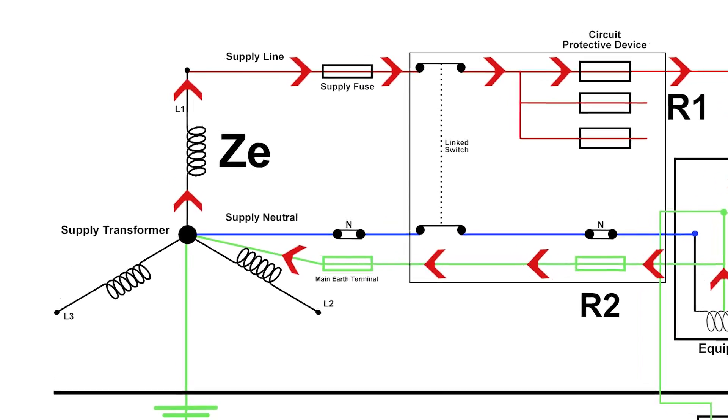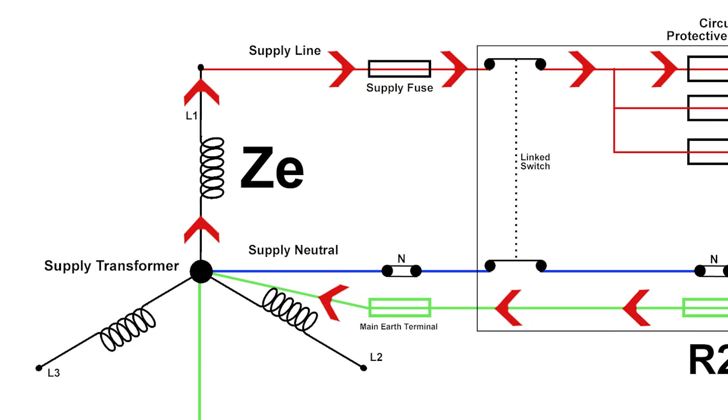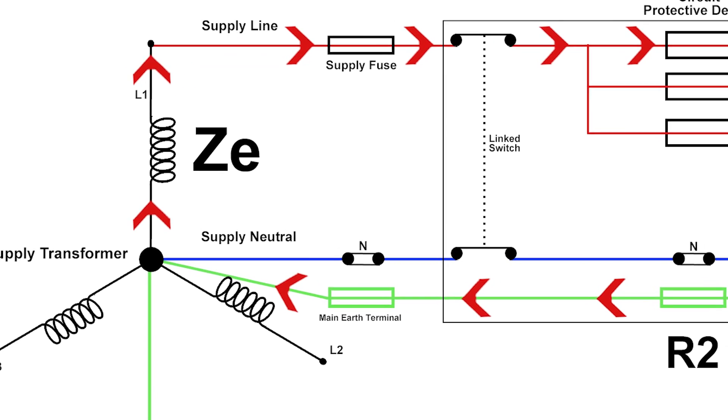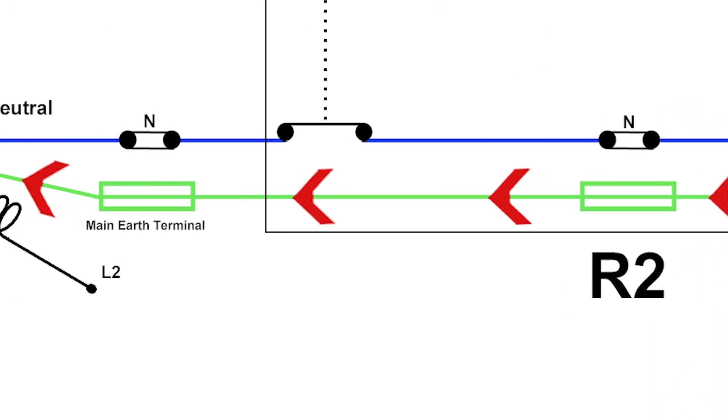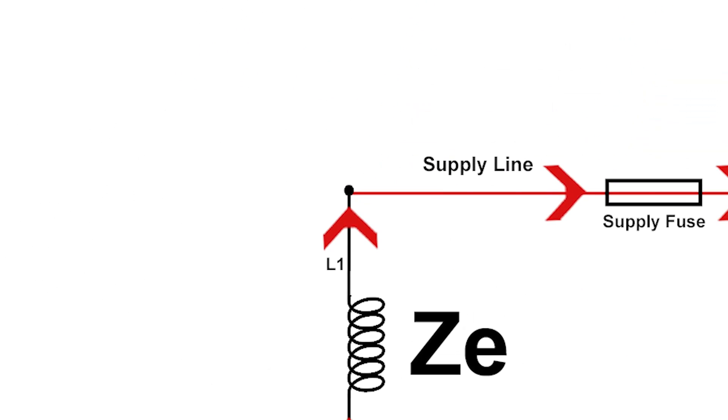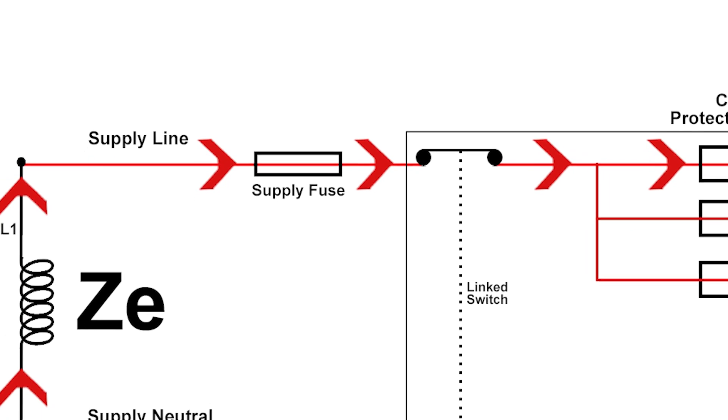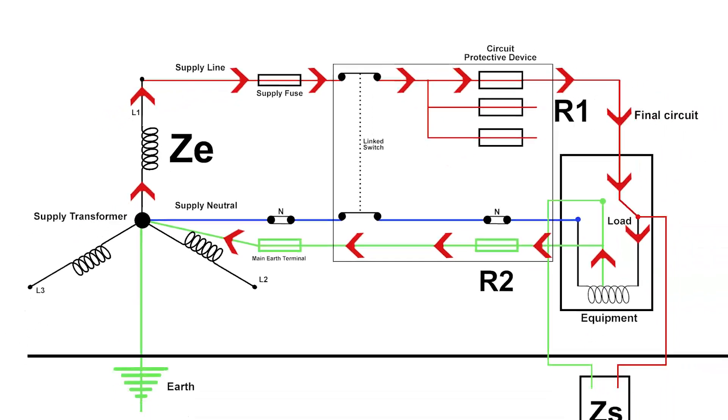Our earthing system is made up of really three components. We've got Ze—the E would be for external, Z is for AC resistance if you like, or impedance. So the resistance of our supply earth and supply line would form our Ze. If we wanted to measure Ze, we would just measure from our disconnected earth at the earth terminal, the main earth terminal, round to our incoming line on our main switch. That would give us Ze, but it's important at that point to disconnect the earth.